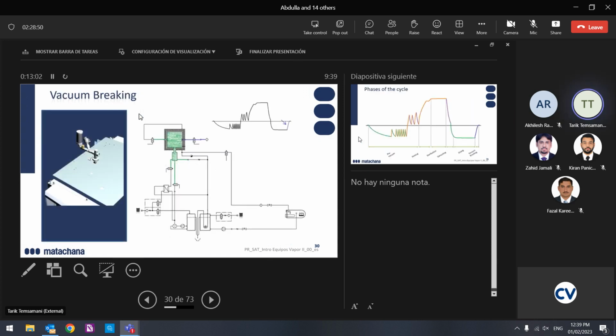Vacuum breaking. What is vacuum breaking? It's the last phase. Once we finish the drying, we have to reach atmospheric pressure in the chamber. The upper valve for atmospheric pressure will open, with the filter. There is a plunger valve, and there is a command to open it. It will be open and the vacuum pump will be stopped. Since the chamber is under vacuum, when we open that, the chamber sucks air from the exterior to reach atmospheric pressure. Once the pressure inside the chamber and outside is the same, we can open the door and the cycle is finished.